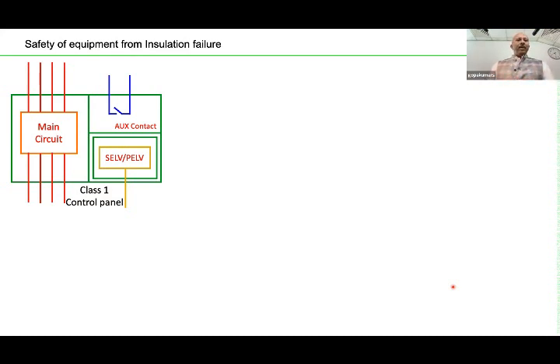Say, for example, between an extra low voltage, as you can see here, the main circuit and the SELV PELV. SELV PELV is, for example, a 24 volt device. Between a 230 volt device and a SELV PELV equipment inside a control panel, we are supposed to have double insulation. Most of the time, these practices are not followed, or very rarely followed, which is also one of the reasons for failure of sensitive electronics. So I hope the picture is clear.